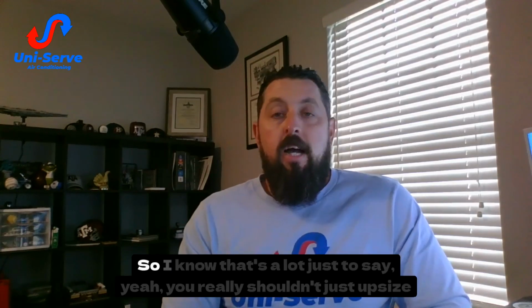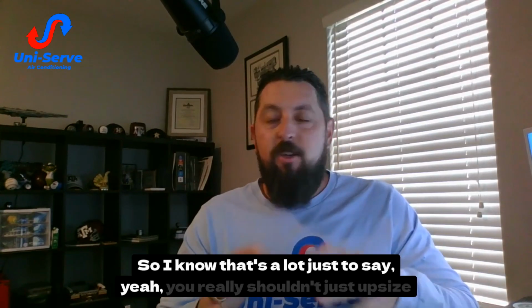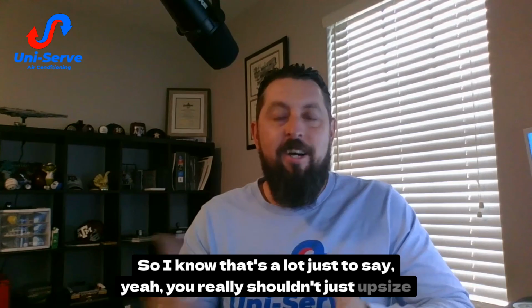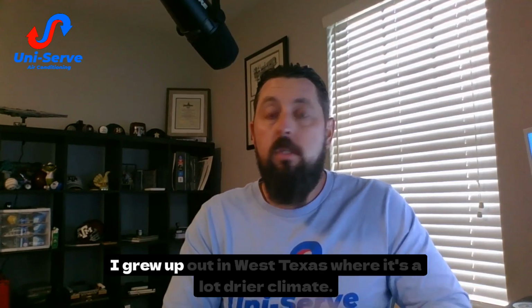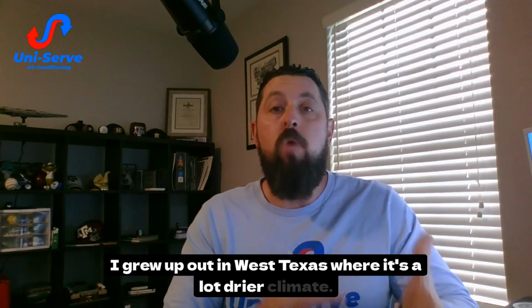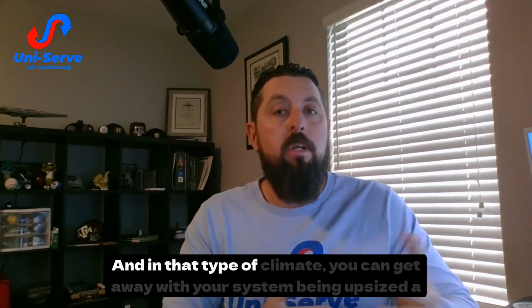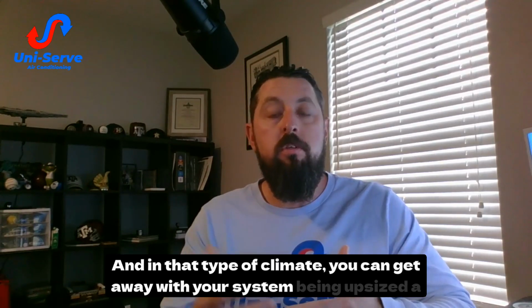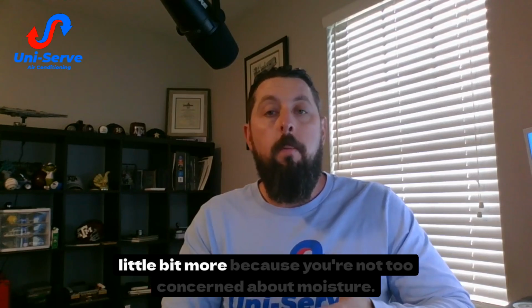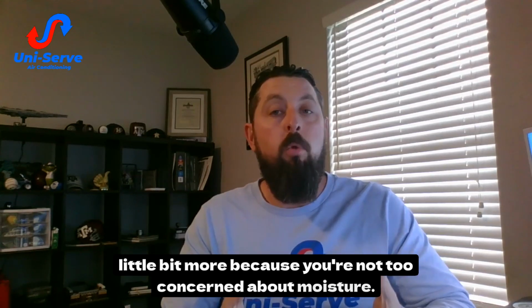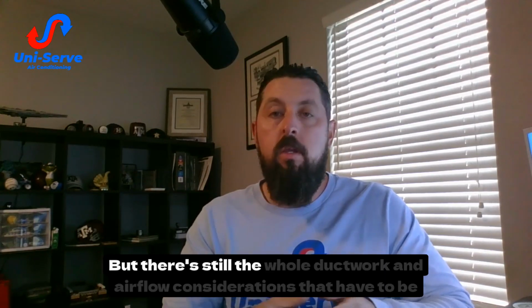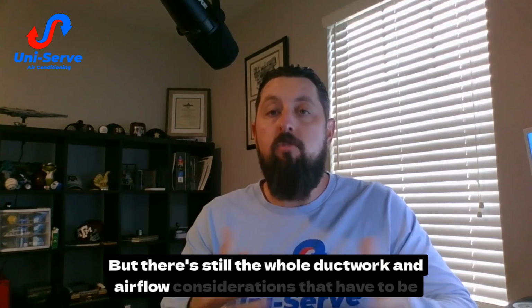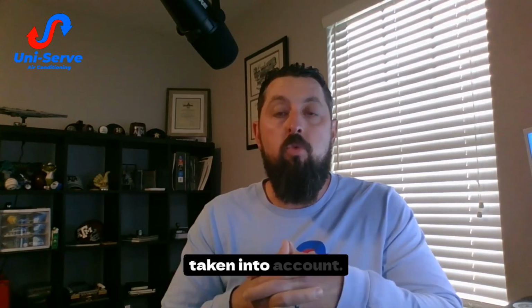So I know that's a lot just to say you really shouldn't just upsize your unit. Now, I grew up out in West Texas where it's a lot drier climate, and in that type of climate you can get away with your system being upsized a little bit more because you're not too concerned about moisture. But there's still the whole ductwork and airflow considerations that have to be taken into account.